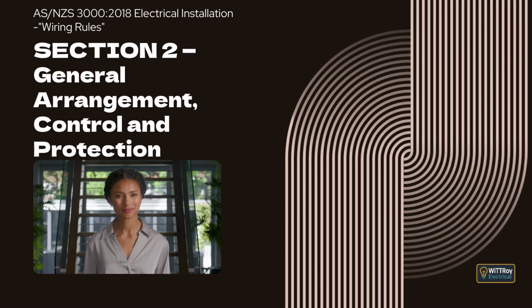Clause 2.2.1.3 Common neutral. This clause explains when a neutral is needed and how common neutrals can be used safely. Any circuit that needs a neutral for the equipment must include one. Sometimes one neutral can serve more than one circuit, but only if all those circuits come from the same supply and if certain safety rules are met. The common neutral must stay continuous and must not rely on the terminals of switches or equipment.